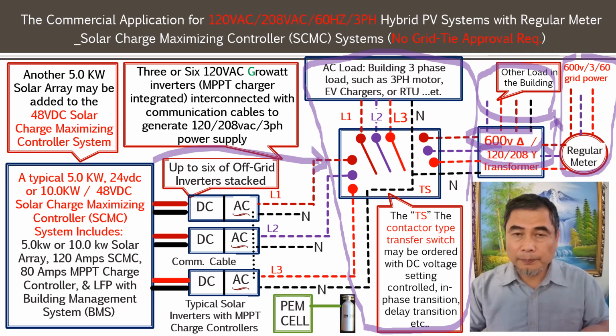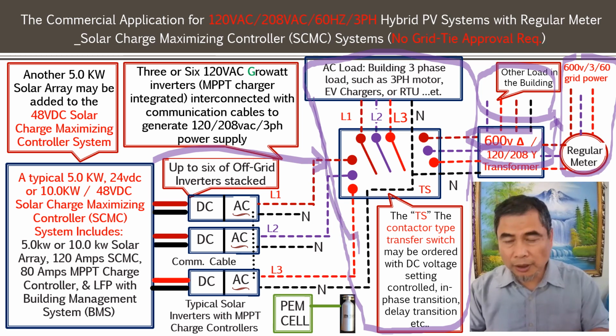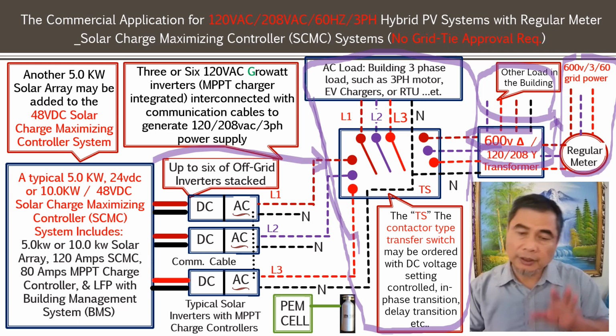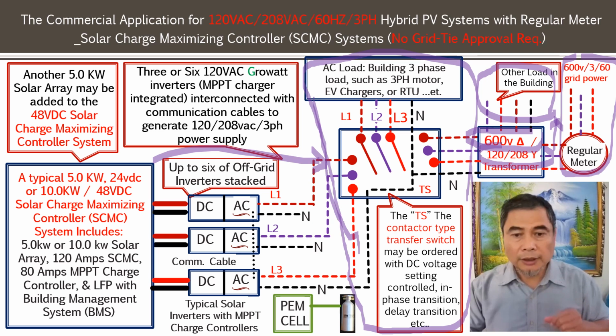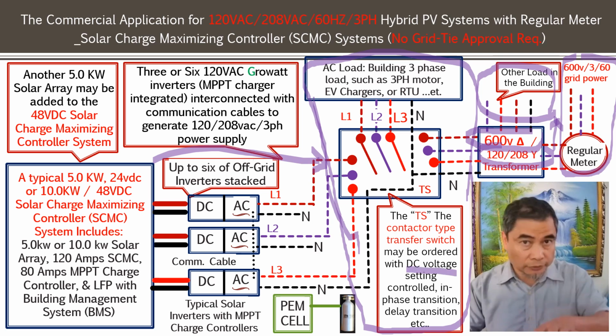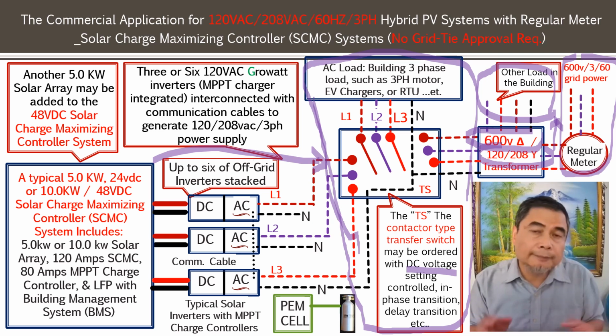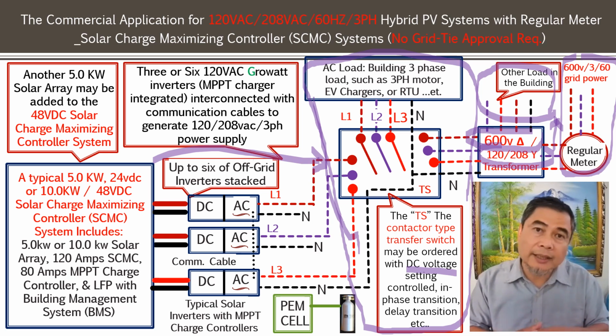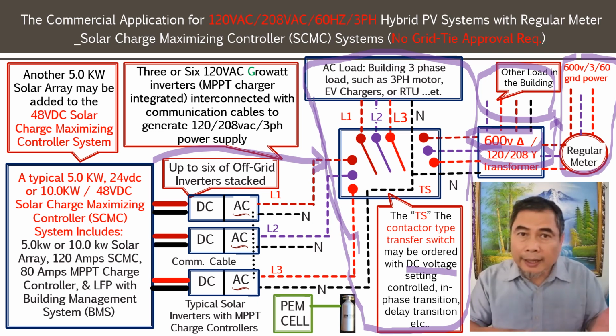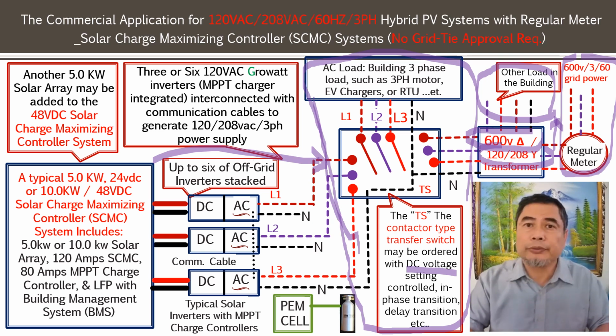When the solar condition is good and the PV system is available, you want the load to be supplied from the PV system. You have a transfer switch built in there. That transfer switch is powering a three-phase load, so you have to make sure it's ordered properly. It's a DC voltage control. As we mentioned, you have the system cut in at 26.5 volts and cut out at 25.5 or 25.6 volts. That's between the 20% and 80% mark, or even up to the 90% mark.